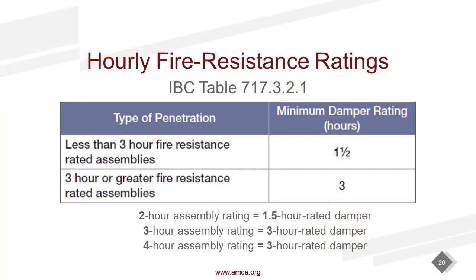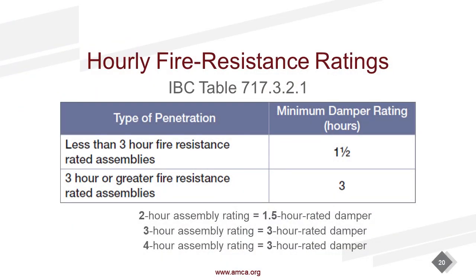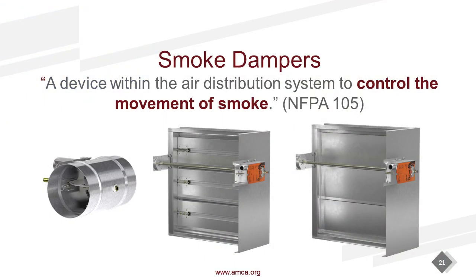All right. So how do we know what the hourly rating requirement is? We simply go to the building code and we know the dampers are tested for 1.5 hours and 3-hour use for fire dampers and combination fire smoke. And the building code simply says, if the penetration is less than 3 hours, use a 1.5 hour damper. If it's 3 hours or greater, use a 3-hour damper. So a 2-hour assembly will get a 1.5 hour damper, and a 4-hour assembly will get a 3-hour damper. There are no such thing as 2-hour and 4-hour rated fire and combination fire smoke dampers in the U.S. I'll go into the out-of-wall in a little bit here. I got that in a couple other slides there. So we're going to jump into smoke dampers.